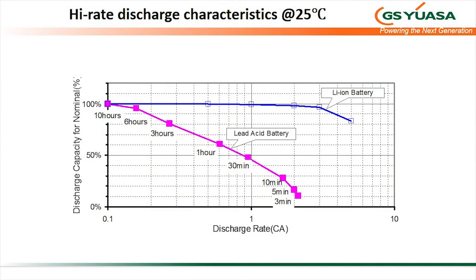With the lithium ion battery, you can maintain that output across almost the entire range of power. So even if you are discharging it at 3 or 4 C rates, you're still getting well over 95% of the available ampere hour capacity. So the key difference, this idea of high power, especially for the cells and products we're making, is a key difference with lead acid, which is probably the incumbent on the UPS market.